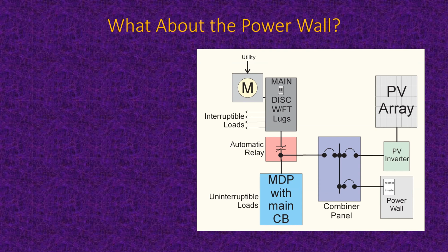If the relay has disconnected the system from the grid, why do we care? We don't care, but the utility cares a whole lot. Because if the system is not disconnected from the grid, that means the solar is going to keep on going, and it's going to be energizing the power lines, which have presumably become de-energized. And if you're a lineman working up trying to reconnect the 12,000 volt feeder that dropped because the pole blew down or something, and all of a sudden somebody's solar system is running, that 12 kV feeder is going to be hot, and you might be very unhappy if you're that lineman. So that's why IEEE 1547 came in. It's really UL 1741 that is the test procedure for that. So that's where that came from.